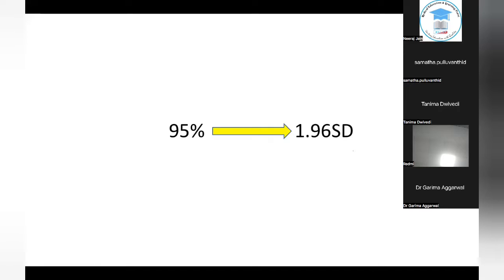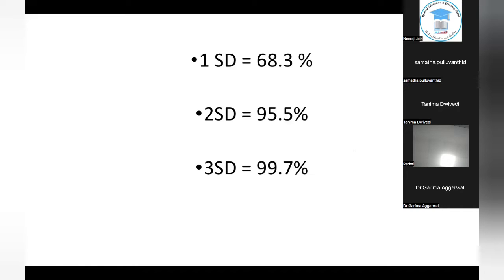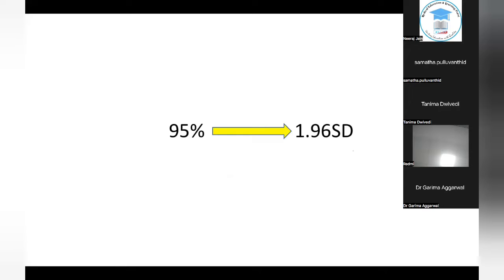The tool for variation is standard deviation, and when we use these 1, 2, or 3, these are coverage factors. 1 SD covers 68.3% of data points, 2 SD covers 95.5% of data points, 3 SD covers 99.7% of data points. So now we are saying 95% is covered by, when 2 is covering 95.5, 95 is covered by 1.96. Therefore, in your references, in your document created by NABL 112, you must have seen they have also mentioned 1.96. This is the reason. Otherwise, it is close to 2 only.